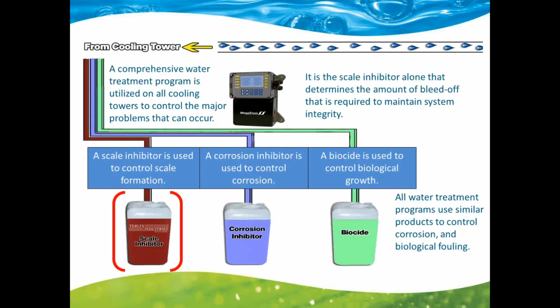A comprehensive water treatment program is utilized to control the major problems that can occur. A scale inhibitor is used to control scale formation. A corrosion inhibitor is used to control corrosion. And a biocide is used to control biological growth. Now, all water treatment programs use similar products to control corrosion and biological fouling. It's the scale inhibitor alone that determines the amount of bleed-off required to maintain system integrity.